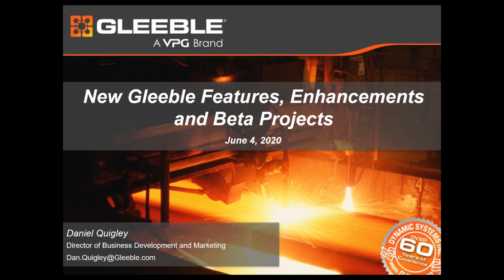There's a question here about, does it show the thermal gradient or profile? And I'm not sure if that refers to the induction heater or what that refers to, but I'll go ahead and try to answer that, assuming that it's in reference to the induction heater. And yes, we can get the same thermal profile in the induction heated sample as we would with the direct resistance heated sample, which we typically do by adding multiple thermocouples to the sample. So we are able to, with the software, filter out the induction heating noise from the thermocouple signal and get obviously a very good thermal temperature reading. And we can then definitely create a thermal profile or a gradient based on wherever you want to put thermocouples on your sample.